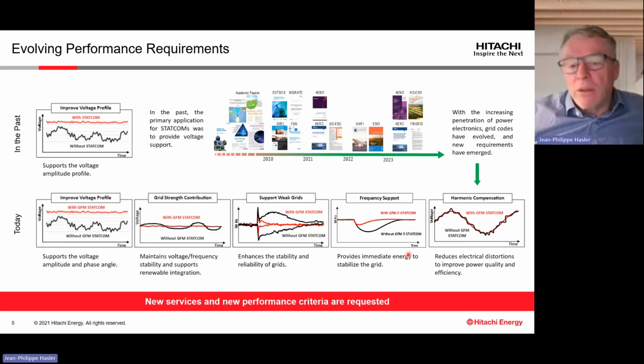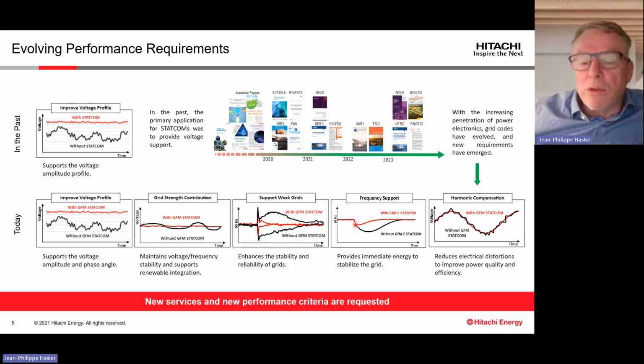Frequency support is typically needed when you lose, as Professor Zakir has shown before, a large load in your system or you trip some subsystem. So we have a frequency nadir, a frequency change, and the functionality of our STATCOM or enhanced STATCOM is to stabilize the frequency. That means to limit the frequency nadir and to restore the frequency faster. This type of frequency support is often related to what some TSOs call an inertia service. That means you provide inertia to the system.